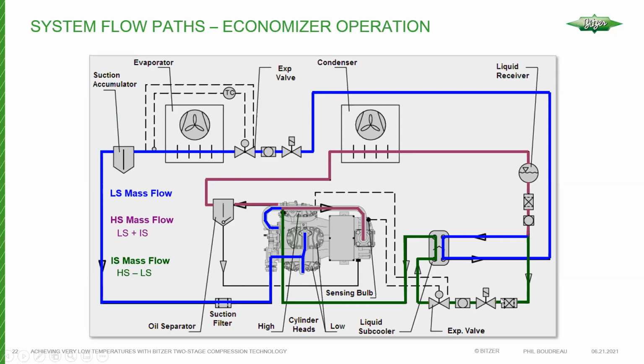So some of that refrigerant travels through another expansion valve, and we'll call this the liquid line accessory kit on the lower right, where it says expansion valve. And this travels through the cold side of the brazed plate heat exchanger, and we're going to evaporate refrigerant to accomplish the subcooling. And then the cool refrigerant that leaves that heat exchanger then enters the interstage mixing pipe. Okay, you can see where that green line enters the mixing pipe, and that's what provides the interstage cooling in this case. And BITZER does have requirements for the superheat that needs to be set at the motor barrel. And just to give you a rough idea, it's going to be approximately, say, 40° R is a reasonable number. You're sensing your superheat at the interstage mixing pipe where the refrigerant enters the motor barrel.